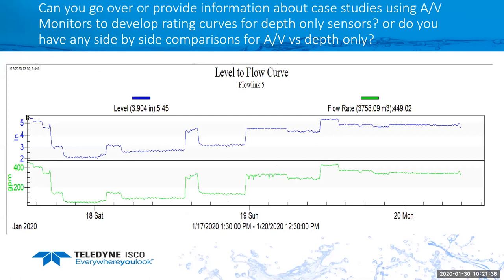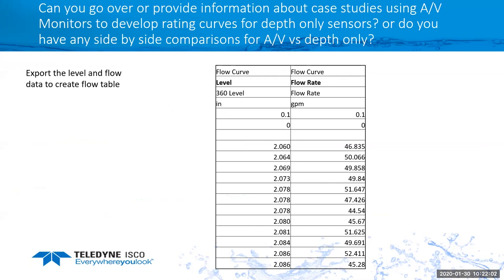What they've done is they've taken an area velocity sensor, put it in the channel, and let it run for a day or a week to get a nice flow curve. With the ISCO FlowLink software, I've taken the level and the flow rate, and as you can see in this example, the level and flow changed quite a bit over this 3-day study. Then I was able to export the level and flow rate to develop a flow table. I exported all that, sorted it, and now I have the option to pick however many level to flow rate data points that I want to use.